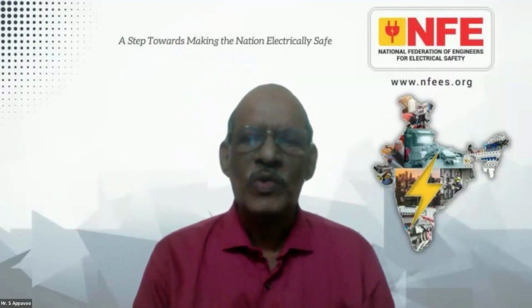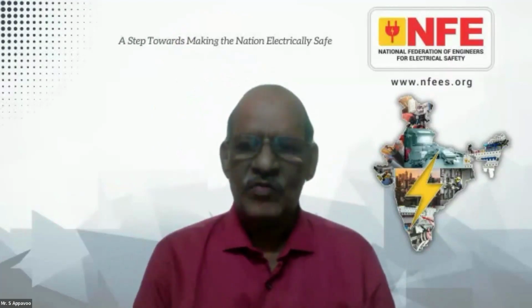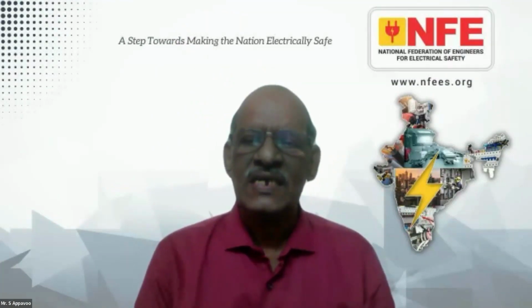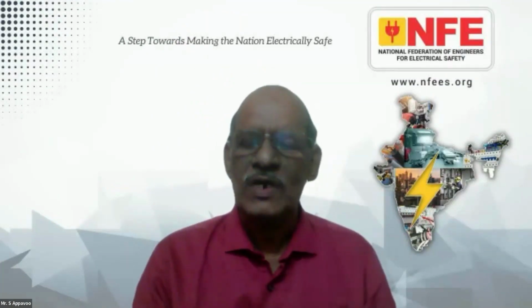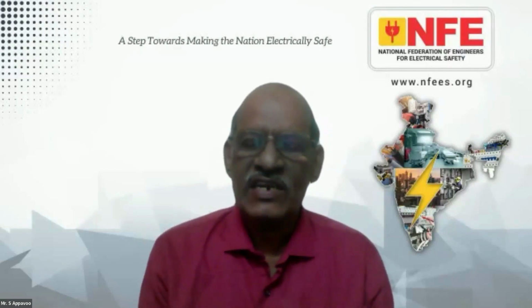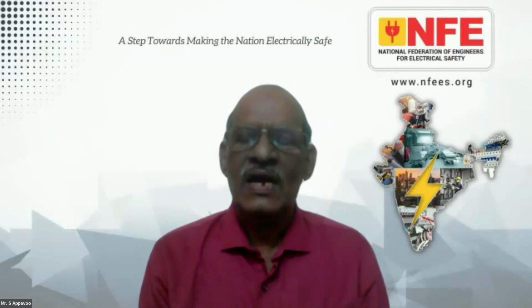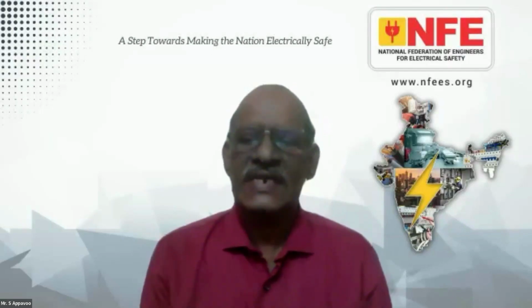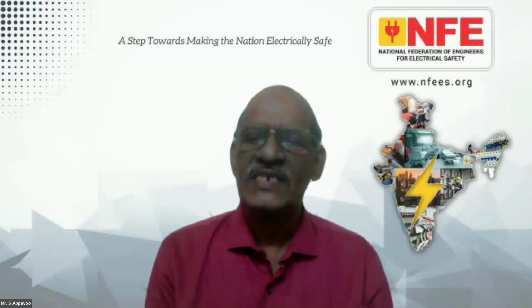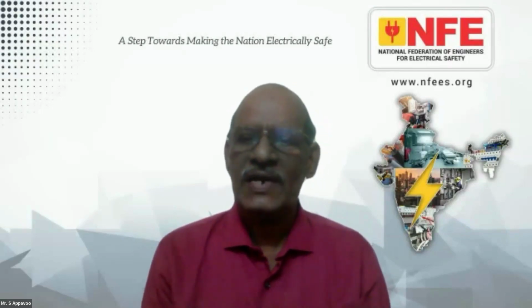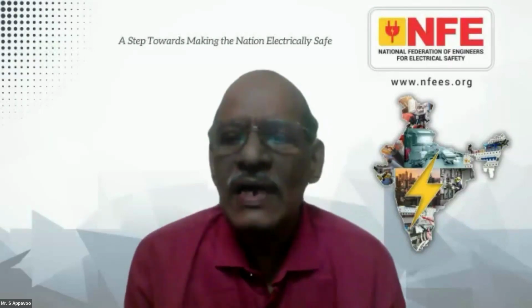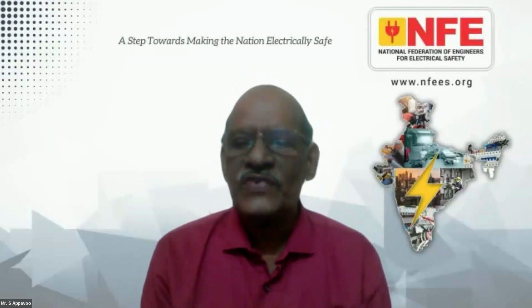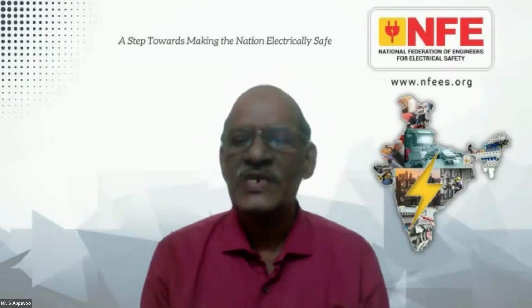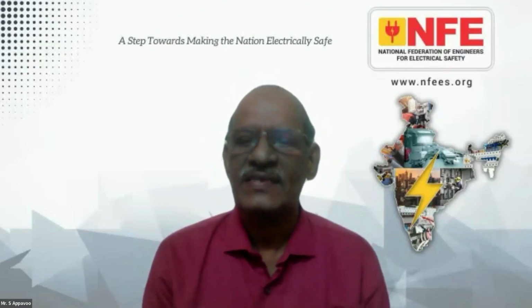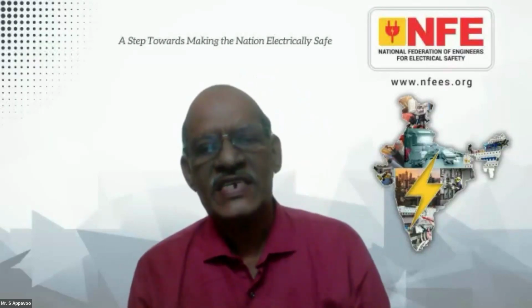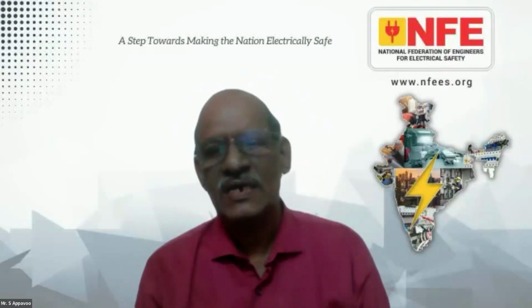That the state government has to notify. This is the thing where several notifications are required to be issued by the state government. One with regard to inspection under Regulation 30, under Regulation 43, under Regulation 34 for the generating plant. Generating plant means it can be a diesel generator or a solar panel. Depending upon the size, it has to be inspected. Now, as of now, with the available arrangement, it is inspected by the electrical inspectors, and a certificate is issued based on which the DISCOM gives interconnection.